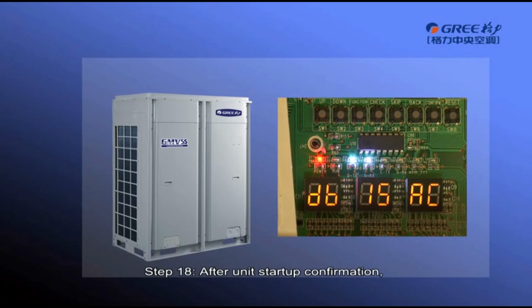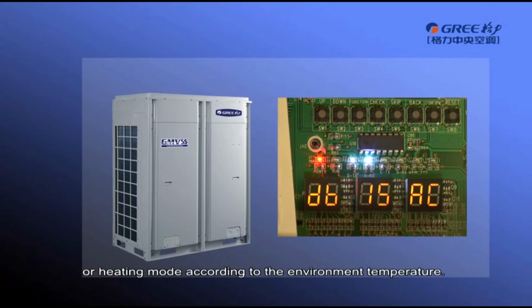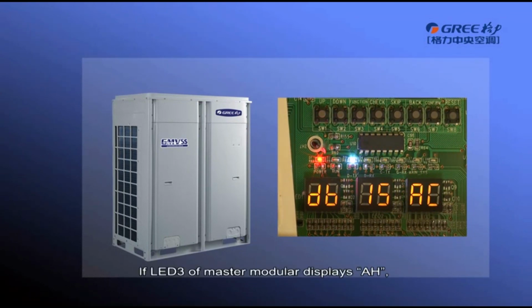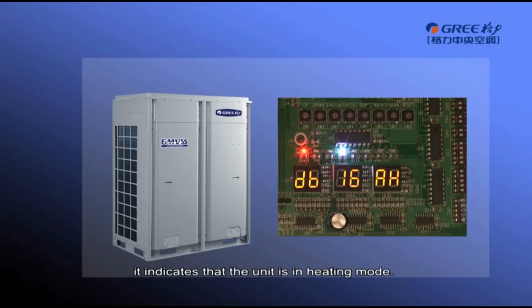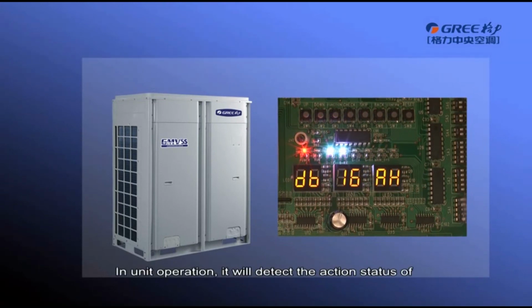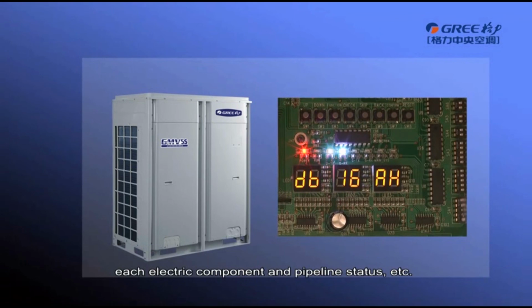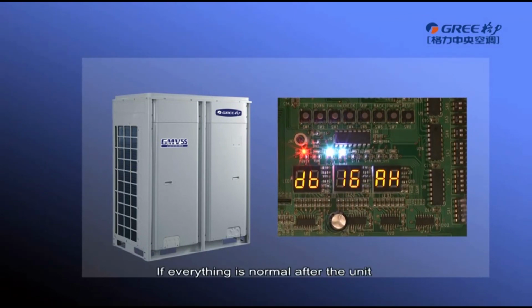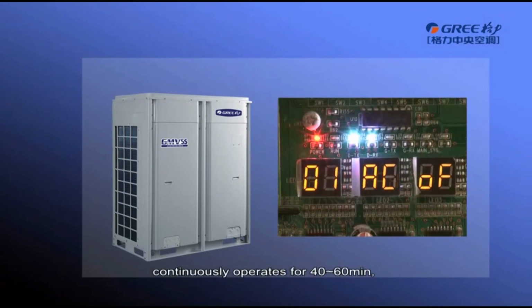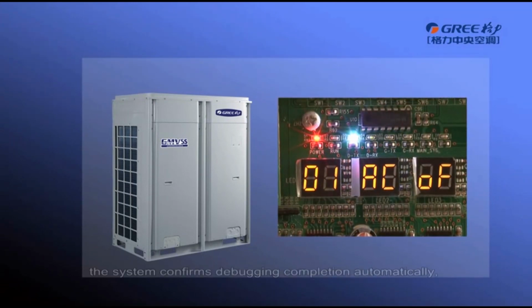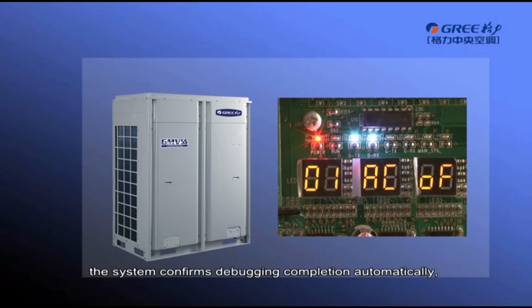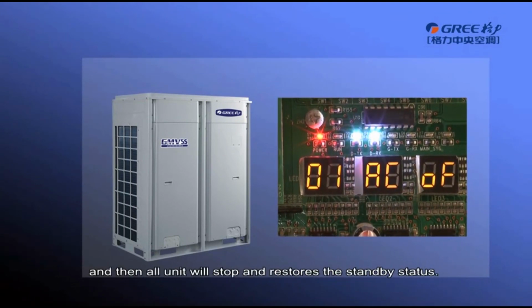After unit startup confirmation, the system automatically selects the cooling or heating mode according to the environment temperature. If LED 3 of master module displays AC, it indicates that the unit is in cooling mode. If LED 3 of master module displays AH, it indicates that the unit is in heating mode. In unit operation, it will detect the action status of each electric component and pipeline status, etc. If everything is normal after the unit continuously operates for 40 to 60 minutes, the system confirms debugging completion automatically. And then all units will stop and restore the standby status.